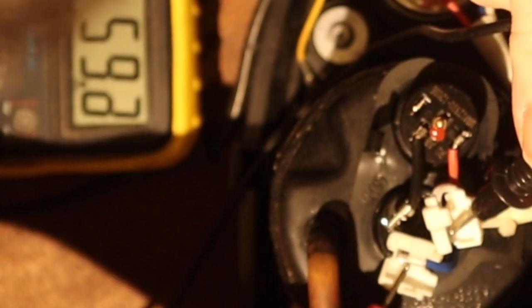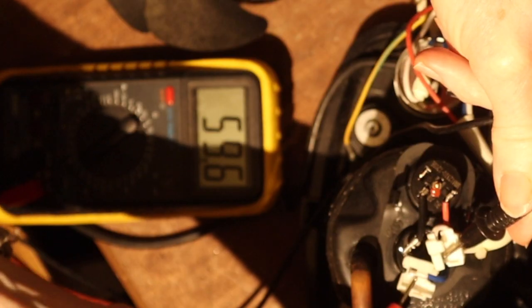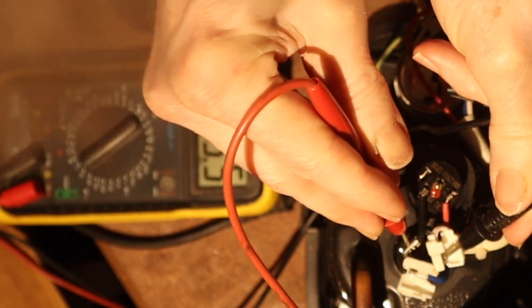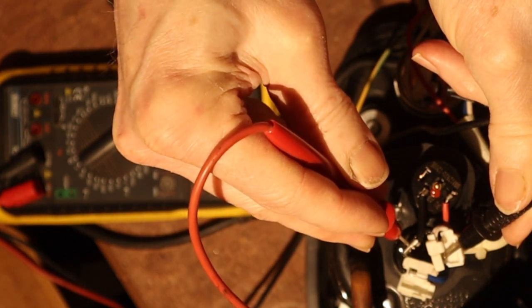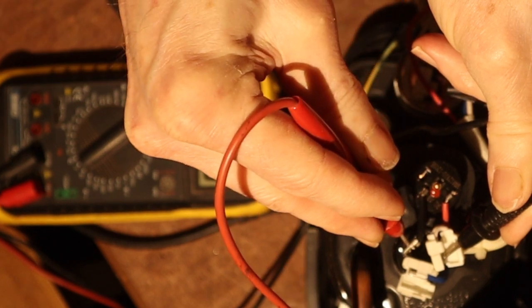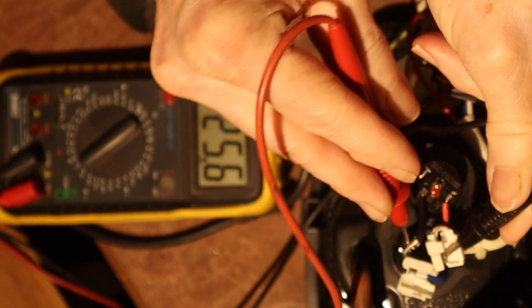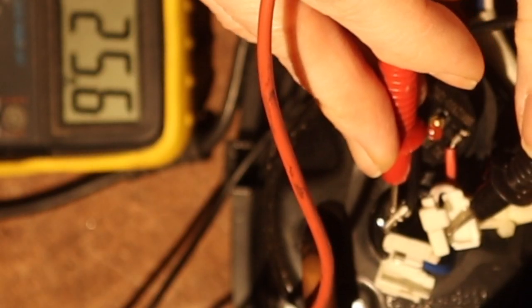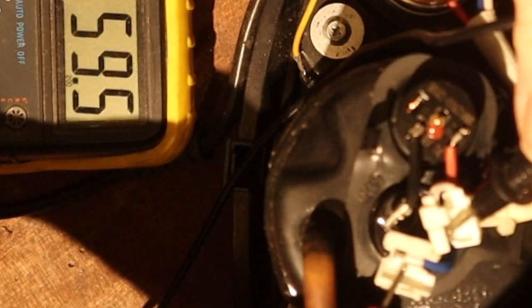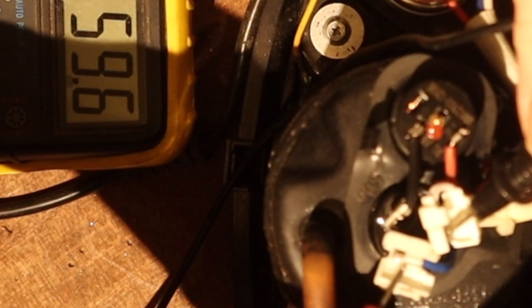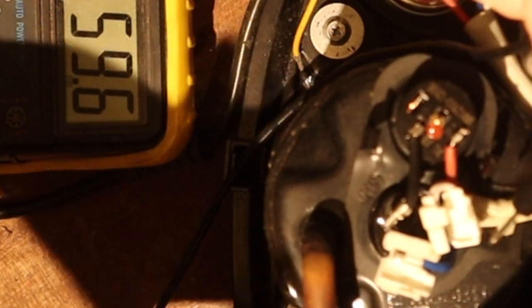So this is 0 ohm. 59.60 ohm - that's the capacitor circuit, the start circuit. And now we have this: that's 25, yeah, that means that's more or less the half, and that means the big power is of course going through these windings. So that is just a confirmation that this is the run winding of 26 ohm, and this is 60 ohm, and that is twice the resistance, which means that's a thinner wire, and that is the start winding. So then we can go on.